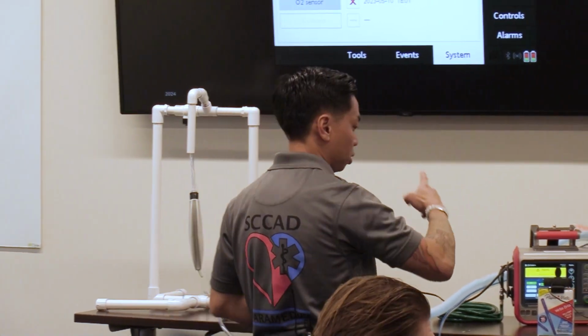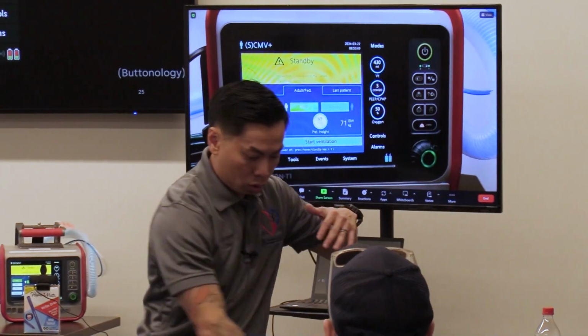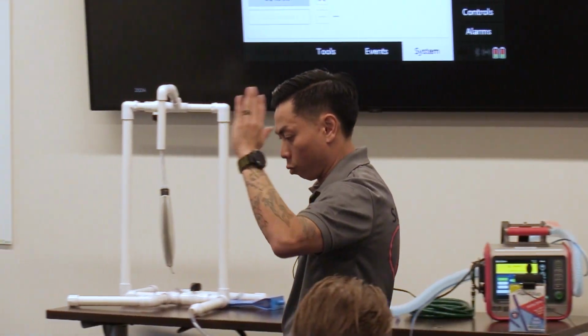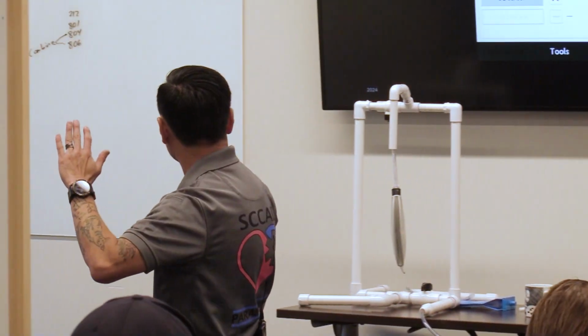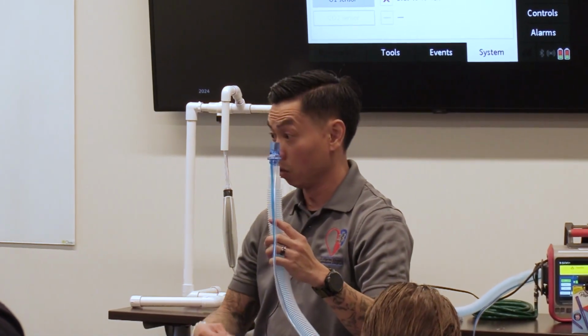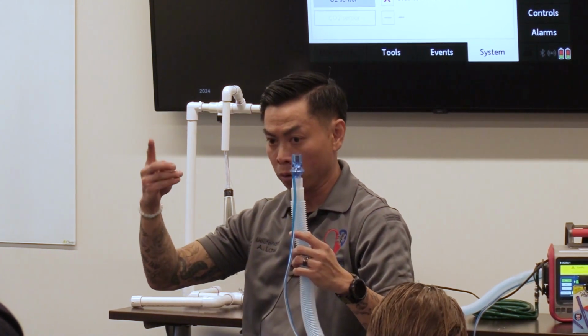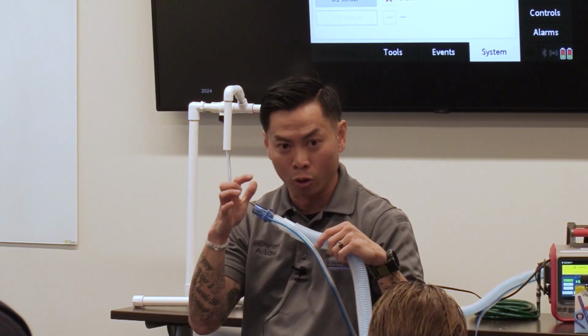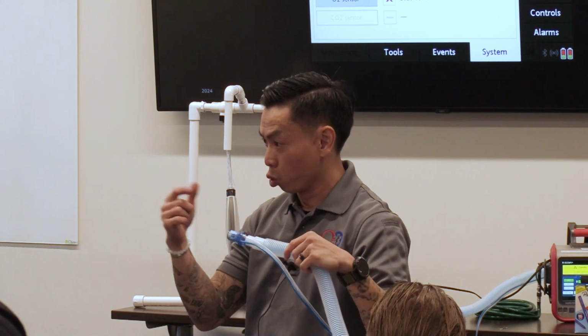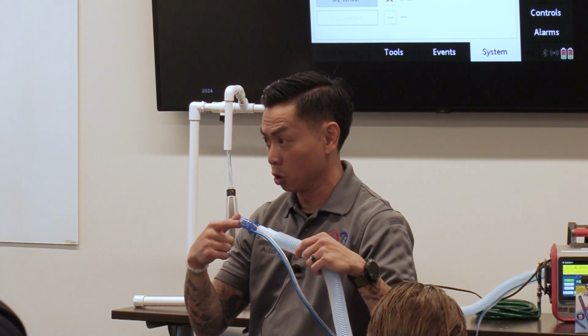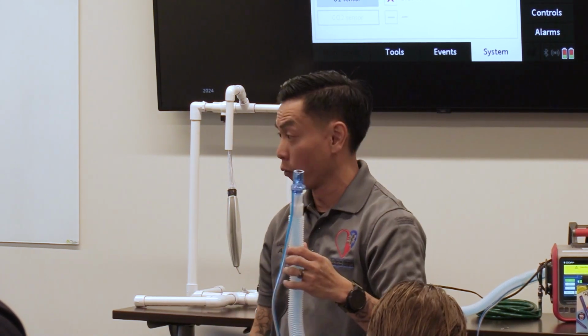The flow sensor test, like we said earlier, is trying to measure the configuration of that plastic valve. So you'll start off with the flow sensor, and then what I'll even do is put the adapter on and leave it open to air, and it sends air through. Don't be the guy that does this or this, right? Because when you do that, you create resistance, and it messes up the configuration. So leave it open to air, and it'll say flip flow sensor.